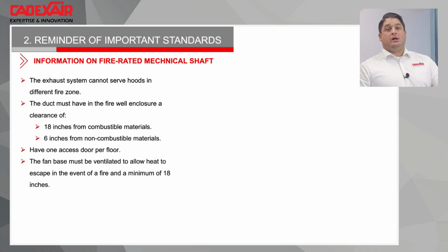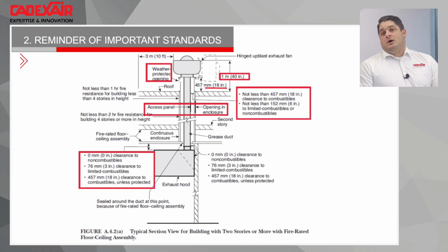The other thing that we talk a lot about is the fire-rated mechanical shaft. In fact, how does it work? I think it's easier to go directly to the picture. The first thing we need to understand about NFPA 96 is you're not allowed to put a hood in two different fire zones. So what is a fire zone? Everything that has been split by a firewall. If you have a commercial strip with three or four restaurants, they will each have their own fire zone, so you will not be able to plug them together. Another example: if you're doing a big hotel with multiple kitchens, you have a restaurant, and often a ballroom kitchen, a production kitchen.